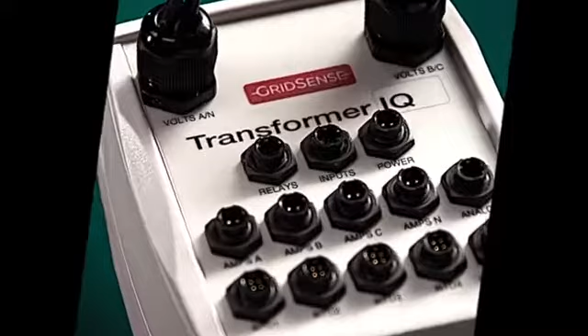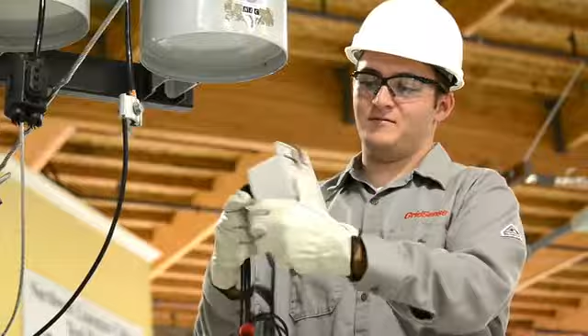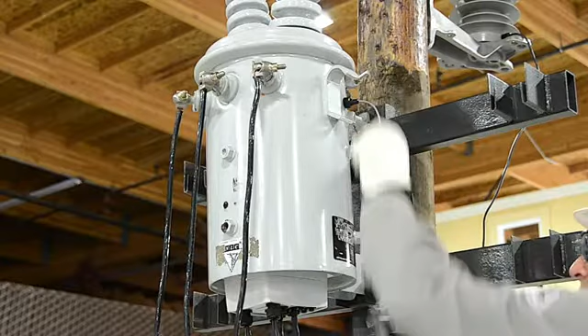The Transformer IQ unit ships pre-configured. The sensors will already be integrated for quick retrofit. The Transformer IQ sensor itself attaches non-invasively to the transformer in seconds with 2 very strong 75-pound magnets. If required, RTDs also attach magnetically for measuring oil temperature. Again, a strong, secure connection.